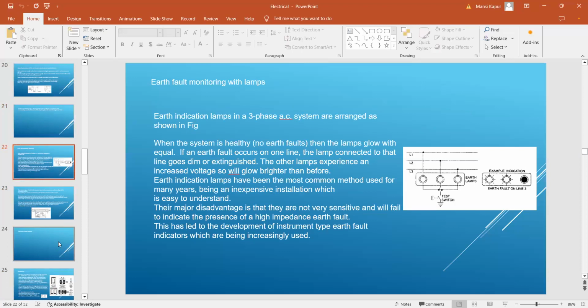So there can be an earth fault monitoring lamp. Have you seen the earth fault monitoring lamp in your ECR? Yes, sir. If you can see in the figure, the first lamp is connected to L1, the second is connected to L2, and the third is connected to L3. At the bottom they have the common point, and this common point is connected to the earth via a test switch. So how to measure the earth fault? Earth indication lamps in a three-phase system is arranged as you can see in the figure. When the system is healthy, that is, no earth fault is present, the lamps glow with equal brightness. When you press this test switch, you are going to get equal brightness.